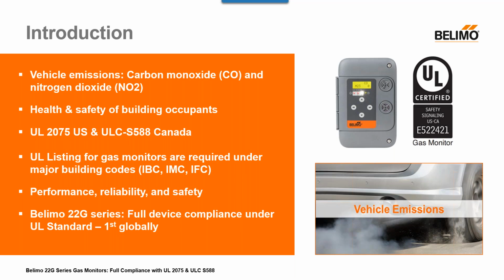And if they do, it is solely for the sensing element component in the device, rather than the entire gas monitoring device. Belimo's 22G series, which includes CO, NO2, and also combination CO/NO2 units, is the first in the world to achieve this full compliance with UL 2075 and S588. The comprehensive certification ensures that every component, from the sensors to the alarms, meets the full scope of the standards. And Belimo's commitment to full system certification provides facility managers and occupants with a dependable, standards-aligned solution for accurate gas monitoring in potentially hazardous environments.